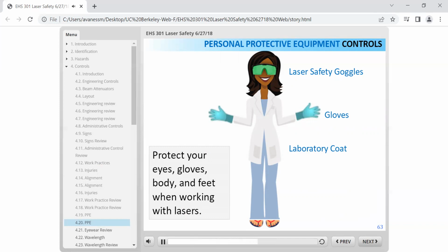Laser light can be attenuated by layered clothing. However, do not wear nylon-based material because it transmits 20 to 40% of light through to you. Use aprons and jackets for protection against UV exposure and fire-resistant materials when working with high-powered lasers. Finally, closed-toe shoes should be worn around heavy equipment that can be moved.